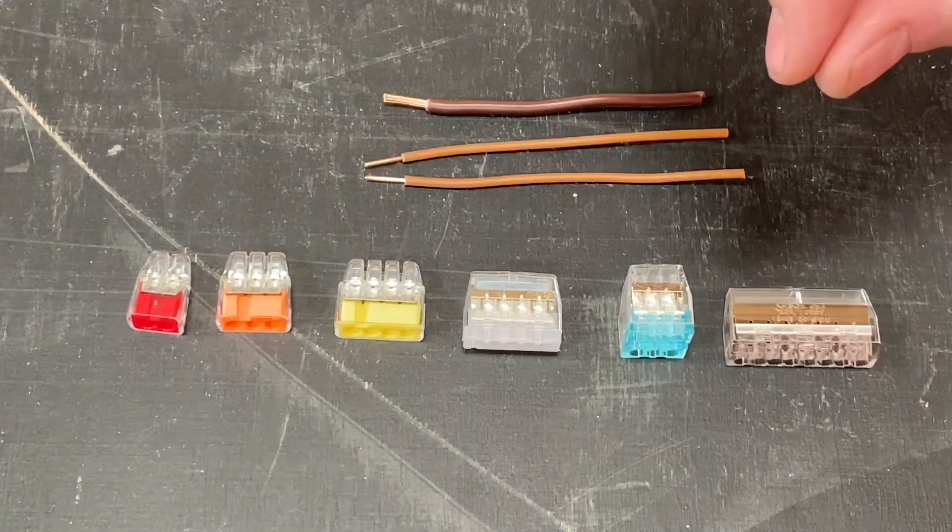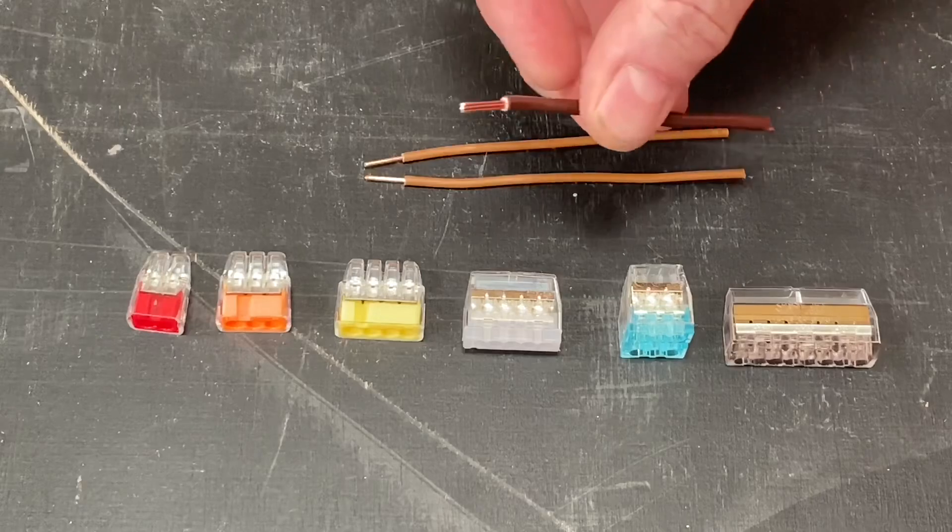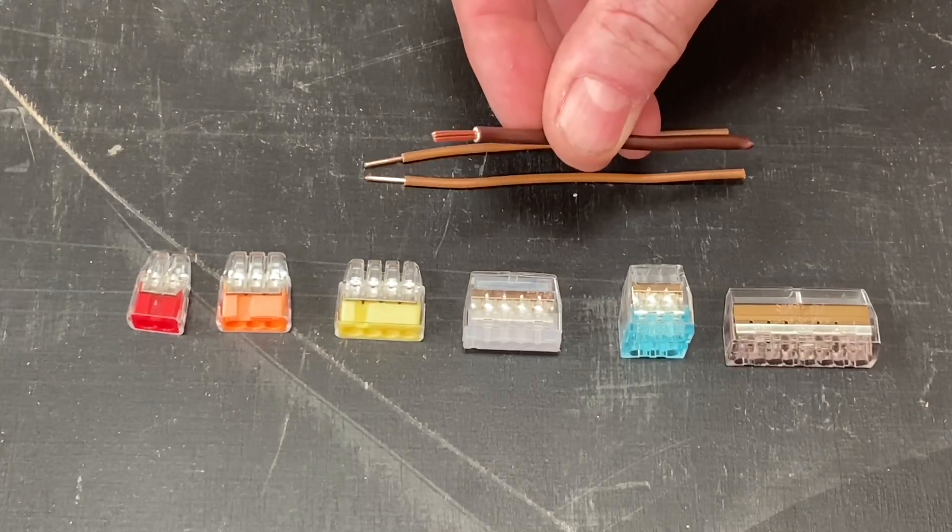They take solid conductors from 0.75 up to 4 millimeters squared, but when we're looking at the stranded variety, they take the 1.5 and 2.5 millimeter squared conductors.